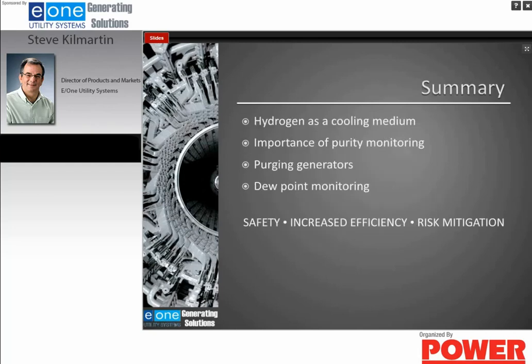In closing, by using hydrogen as a cooling medium, you can get more megawatts without increasing the size of the generator. More megawatts means larger generator, bigger generator, more iron, more heat. For reasons concerning safety, efficiency, and risk mitigation, it's very important that we know what the purity of the hydrogen is. Before purging, we need to make sure that our standard operating procedures are up to date.